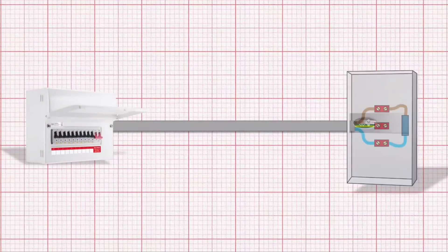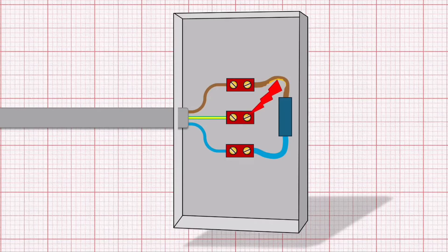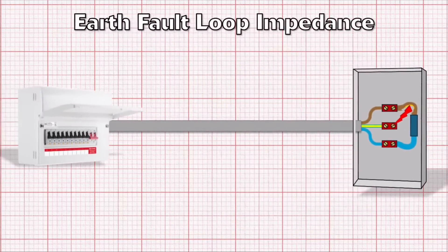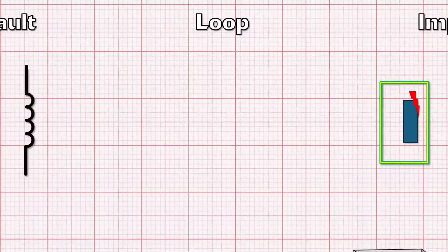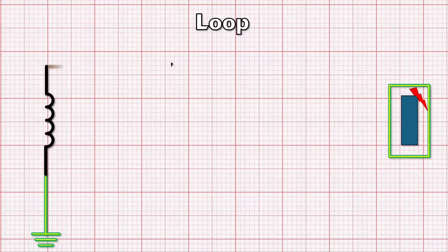But what about when something goes wrong? Let's say a fault occurs and the line conductor comes into contact with the circuit protective conductor via an exposed conductive part — that's the 'earth fault' part of earth fault loop impedance. The 'loop' part describes the path that the current caused by the earth fault will run through.